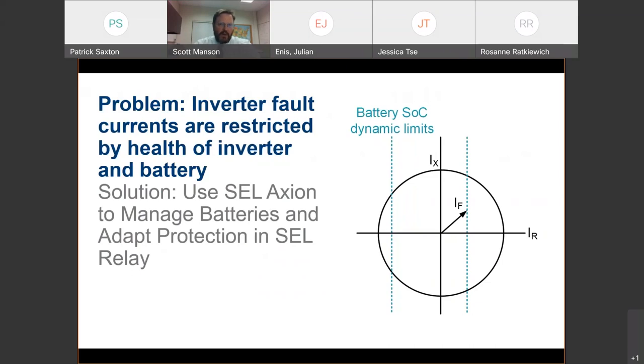If this doesn't work right, you have only one choice. This means, for example, if you have a single fault on a low voltage circuit, the moment that fault occurs, the whole power system must go out. Because if you can't safely protect it with a coordinated protection system, then there's only one answer. It's binary. Everybody loses power. Now, that's a fragile grid. That's the very definition of a fragile grid. So what this creates is a fragile grid that can be solved using intelligent relays and electronics throughout the power system. That's the only way we found to solve it.